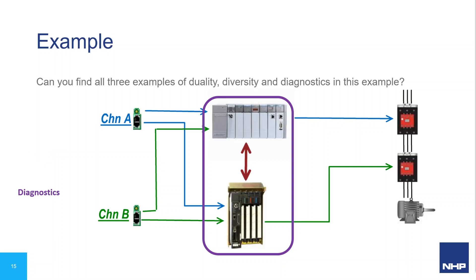For diagnostics, the two PLCs interact with each other, ensuring that inputs from the limit switches are detected by the other PLC and that the logical output is the same. They also check the health of the other PLC. If a fault is detected in either, the healthy PLC will bring the system to a safe state.